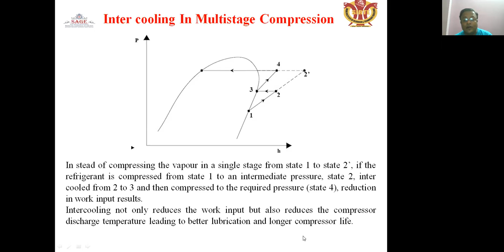a longer compressor life. Intercooling using an external water-cooled heat exchanger, where the diagram shows the low stage compressor requiring low work, and after the compression it goes to the water-cooled heat exchanger where it is cooled, by exchanging heat between two fluids. The surrounding fluid is water, and the refrigerant is losing heat here. The water comes in cold and goes out hot, in a reverse manner. The refrigerant coming from the low pressure side takes up the high temperature heat, and loses heat to the surrounding fluid.